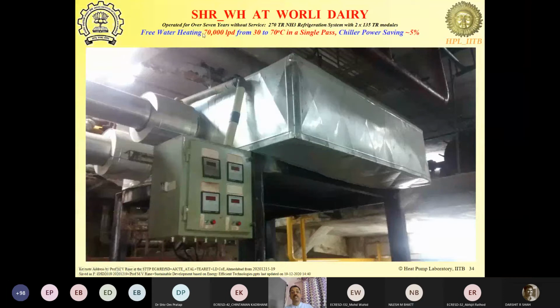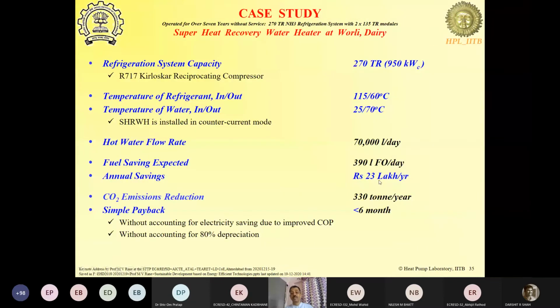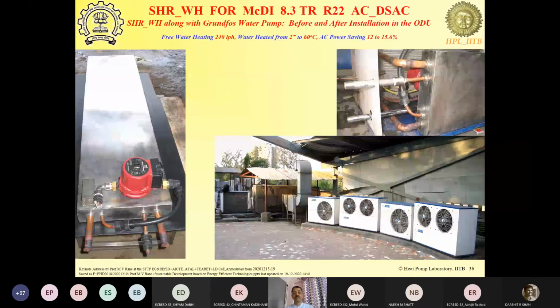At Worli Dairy, we did another project where 70,000 liters of hot water was generated. Both the ammonia and the water side were made out of stainless steel tubes of 1/4 inch diameter. Okay, and the chiller power consumption went down by 5%, and the hot water recovery was of course free. A 140 horsepower pump on the condenser water cooling side could be shut off because of that. And of course, they saved water in the cooling tower because this much of heat was recovered here. So again, here the payback period promised was less than 6 months, and they actually got it in less than 6 months. Saving was 23 lakhs per year, while the install cost was only 10 lakh at that time. Okay, this also operated for more than I think 8 to 9 years without any difficulty.